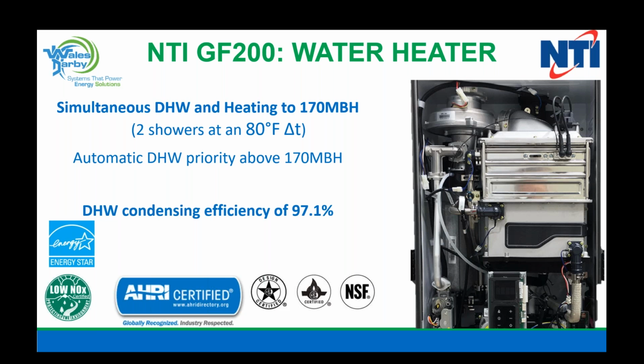It will deliver simultaneous hot water and heating until the unit reaches 170,000 BTU. Once it gets to 170,000 BTU, it will automatically prioritize the hot water, and it will continue to drive itself up to the 199,000 BTU of input that it's capable of. Okay, so we have a combination furnace with 97.1% efficiency. So the Energy Star, the rebates that are available, everything that's out there as far as dollars back to the homeowner because of that 97.1% efficiency rating, that really helps when you're proposing a new installation or a retrofit installation, and the homeowner sees the opportunity to save some money with the rebates that are available.